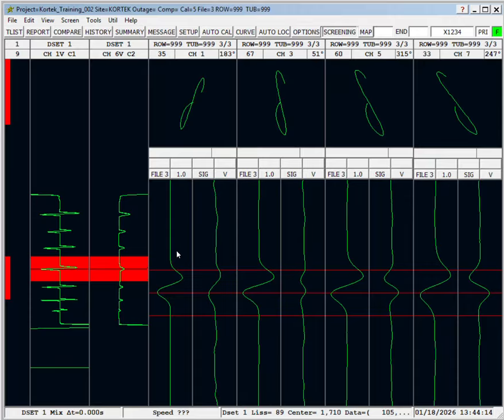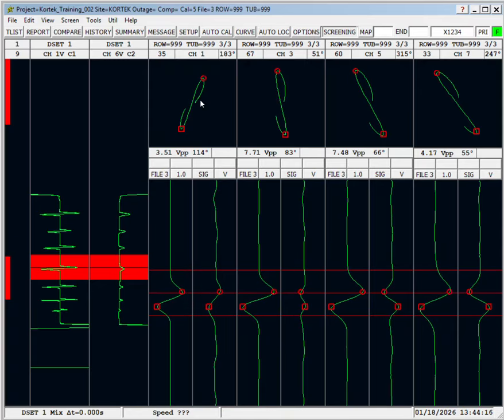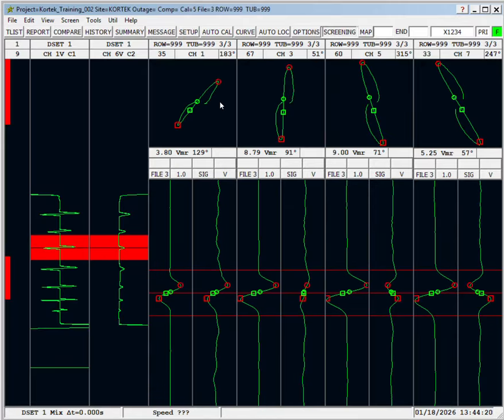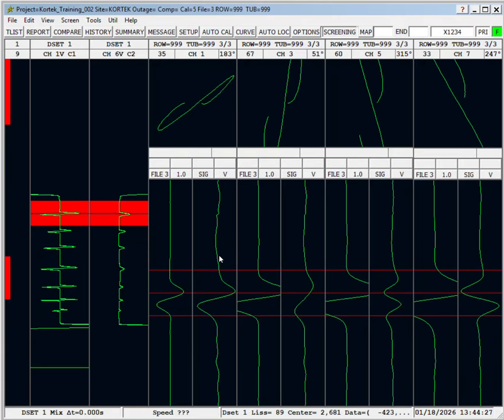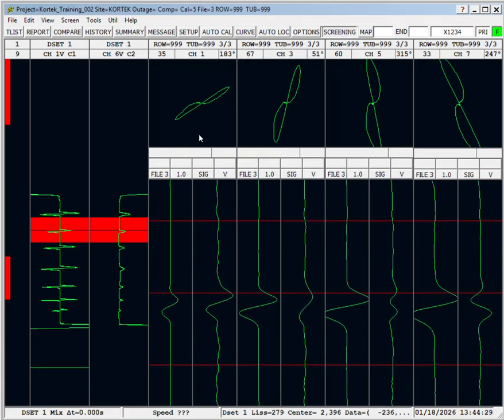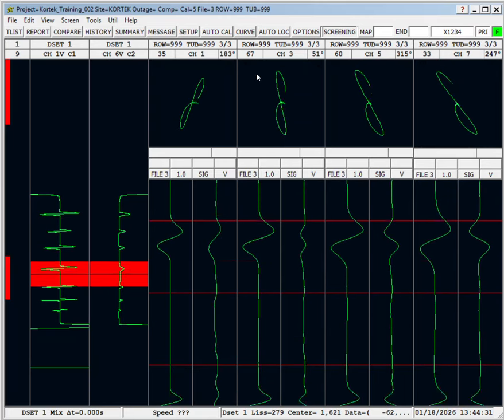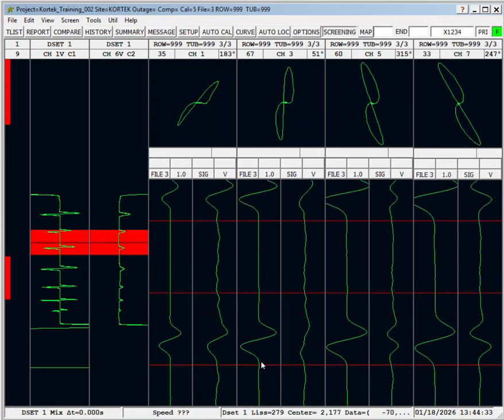Next, we have the 60, does the same thing, rotates counterclockwise with decreasing test frequency. Then we've got the 40, then we've got the 20s, and then we've got the 20% OD groove. So notice how all of the OD flaws share common characteristics.